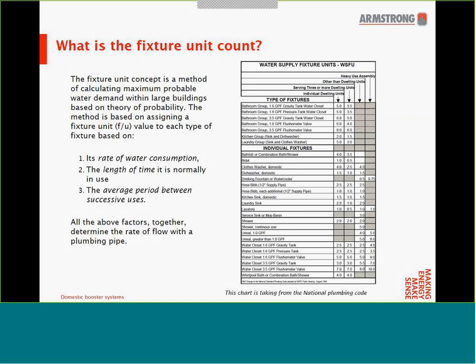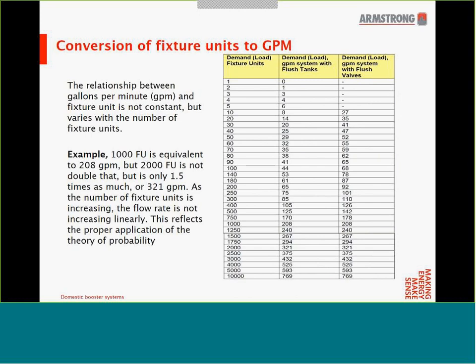For example, when converting a shower used in an individual dwelling into a fixture unit, we would typically need two fixture units for every shower. We go through the entire building inventory list and convert all the water fixtures into equivalent fixture units. It should also be kept in mind that when calculating the maximum probable water demands, fixture unit values are always added — not the GPM values.